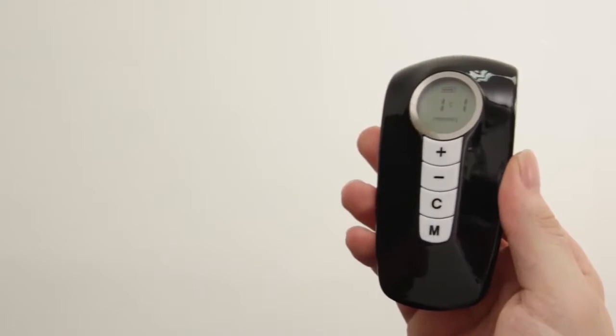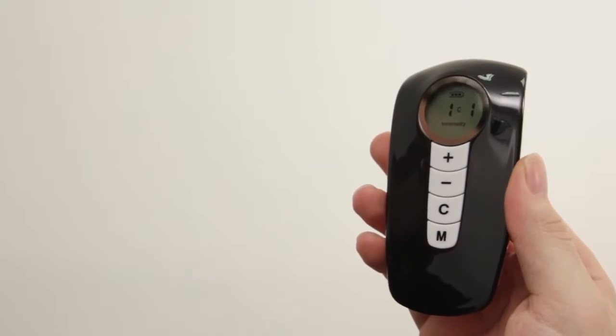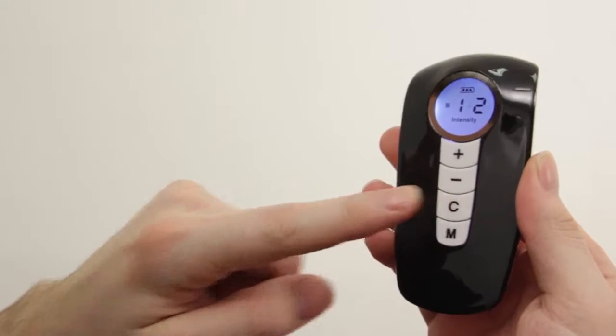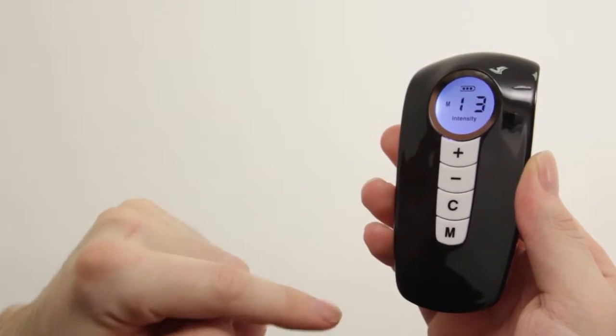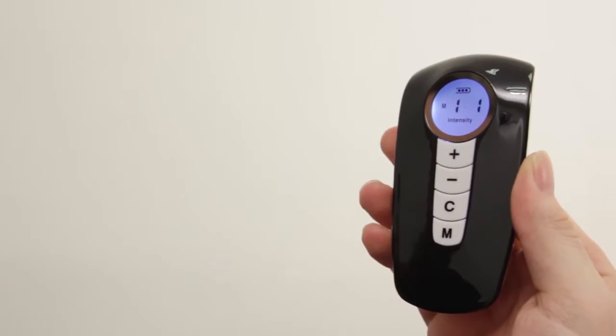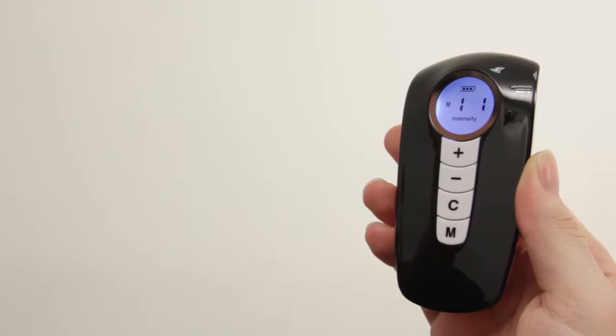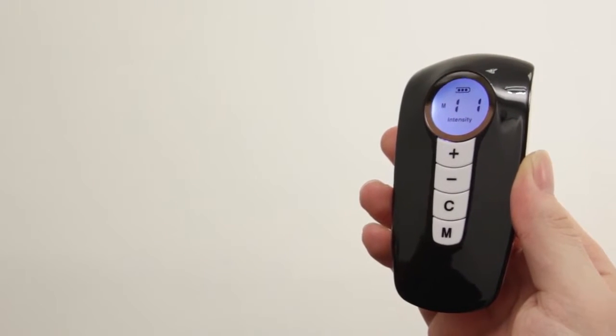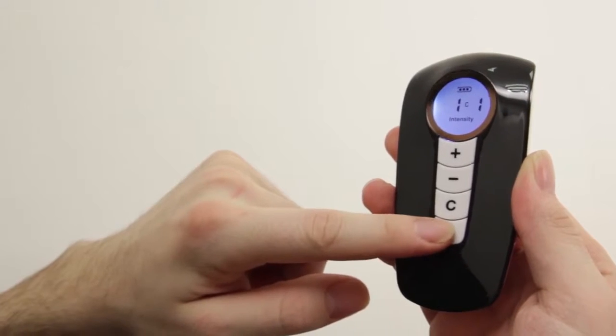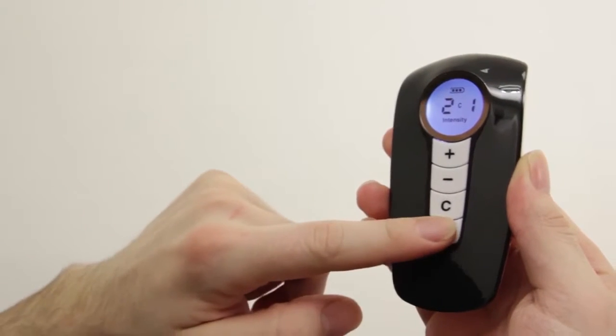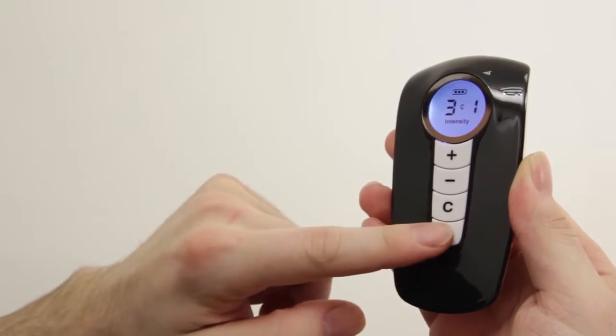Now it's time to start using your TENS machine. Begin by choosing the channel for your module using the C button. Here we select Channel 1. Next, the wireless TENS and EMS system has 4 modes or treatments available. By pressing the M button on your remote, you will change the mode.